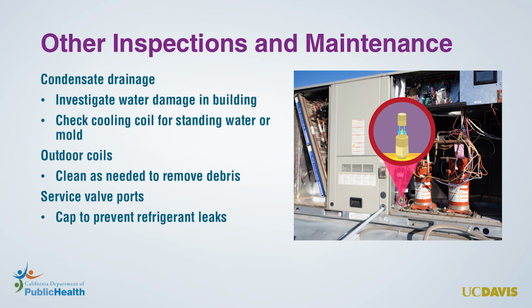Finally, while inspecting your HVAC systems, ensure that the service valves for the refrigerant circuits are capped with brass gasketed caps. These valves are generally spring-activated Schrader valves and are often missing caps. You should be able to locate them near the system compressors. Capping these valves prevents refrigerant leaks, which is important for system efficiency and performance. Refrigerants are also potent greenhouse gases that should not be released to the atmosphere.